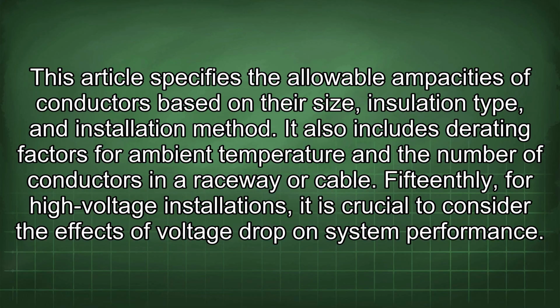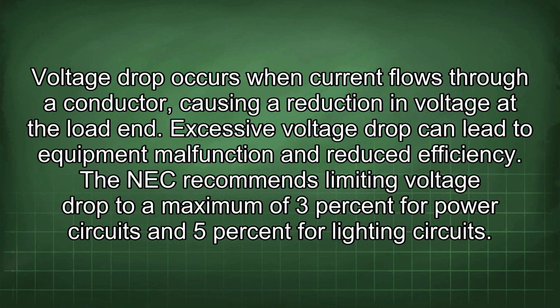15thly, for high voltage installations, it is crucial to consider the effects of voltage drop on system performance. Voltage drop occurs when current flows through a conductor, causing a reduction in voltage at the load end. Excessive voltage drop can lead to equipment malfunction and reduced efficiency. The NEC recommends limiting voltage drop to a maximum of 3% for power circuits and 5% for lighting circuits.